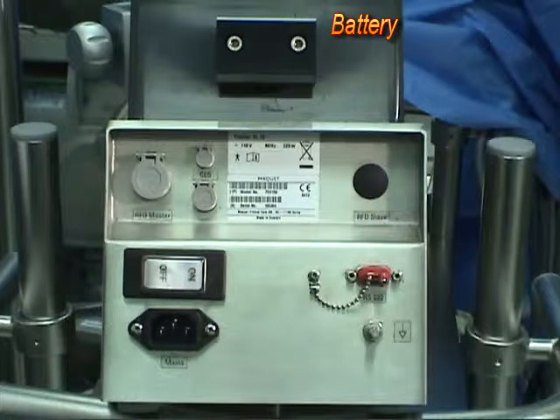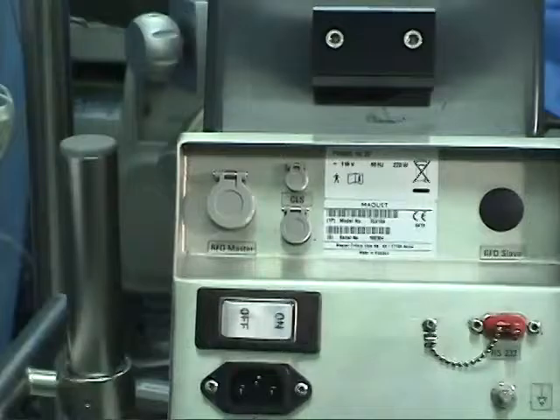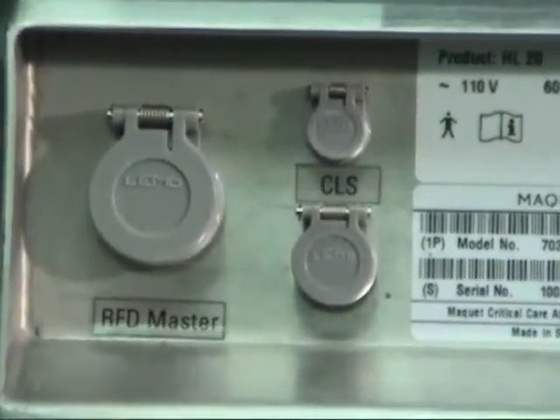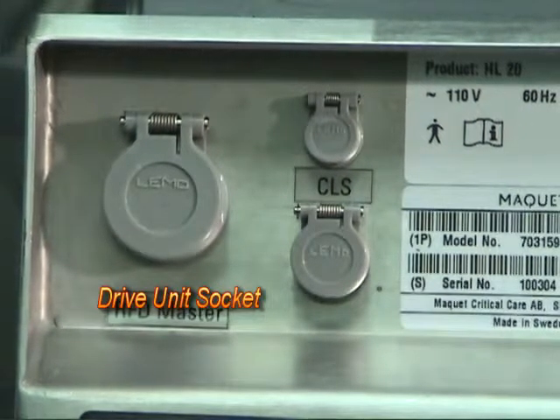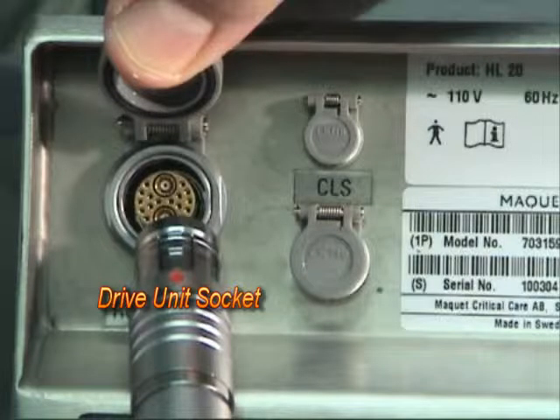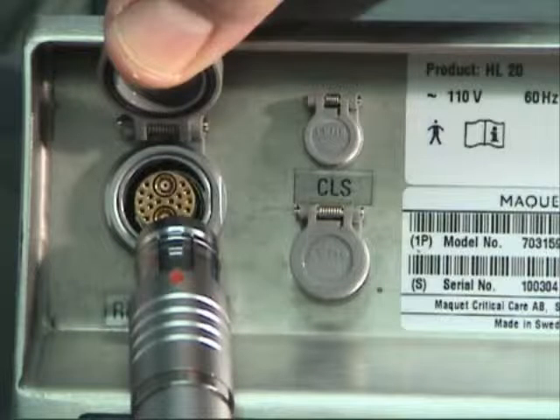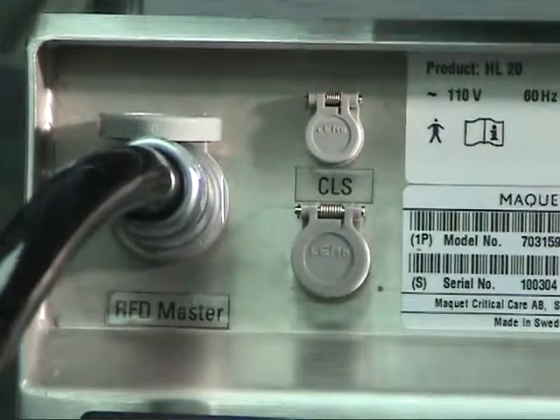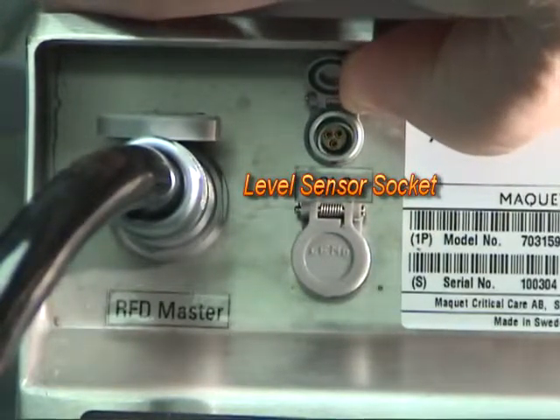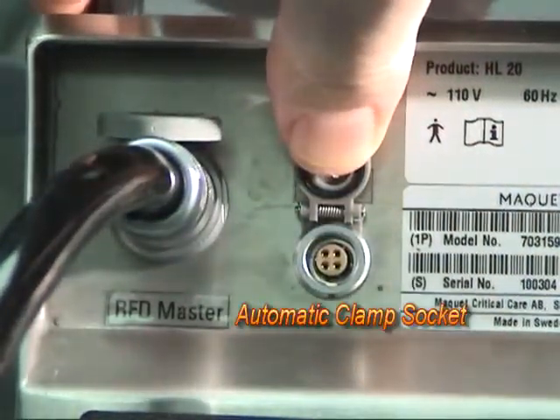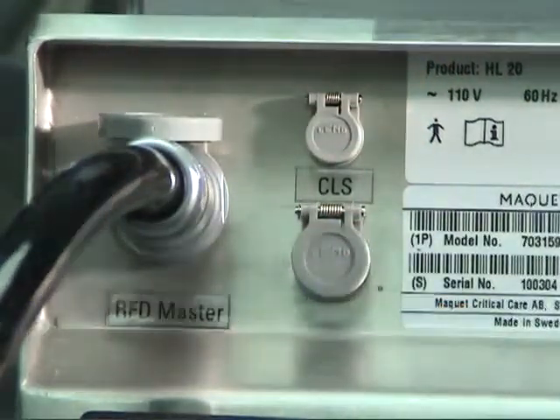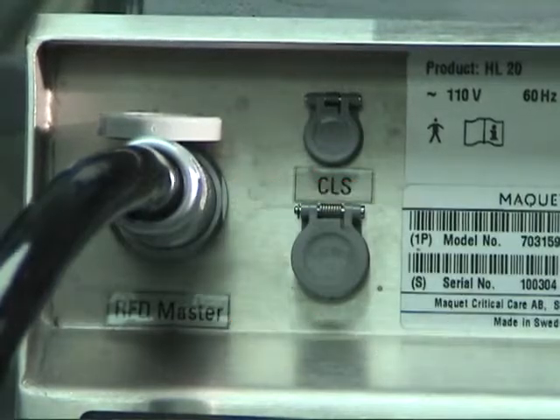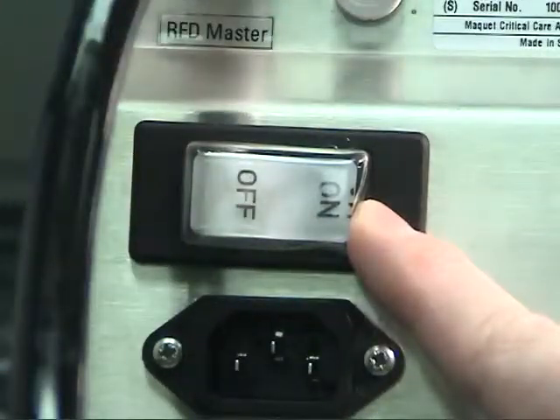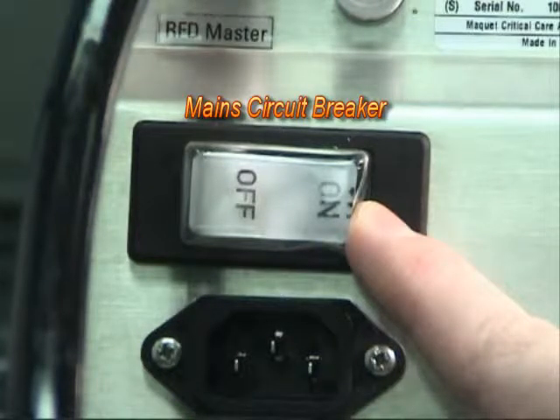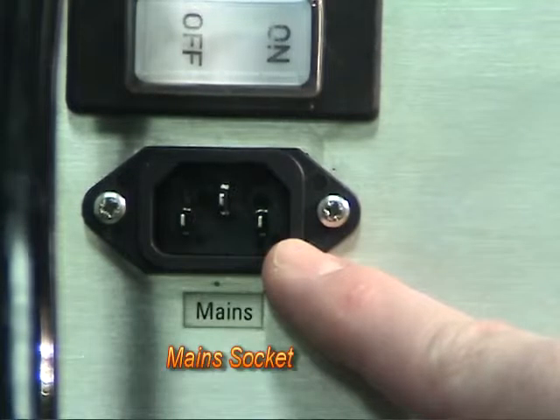From the rear, on top, you can again see the back side of the battery. Moving down and from left to right is the RotaFlow drive socket. This is where the external motor is plugged in. Followed by the level sensor socket and the automatic clamp socket. On the bottom of the unit, you find the mains circuit breaker and the mains socket.